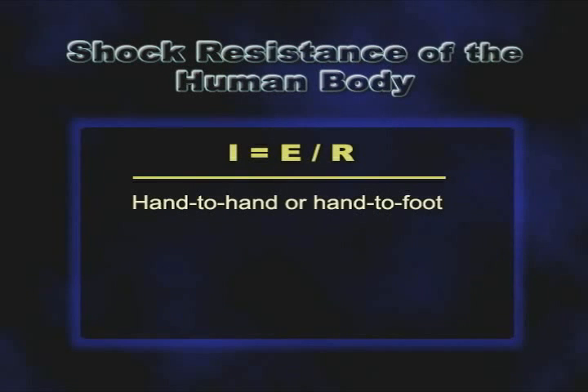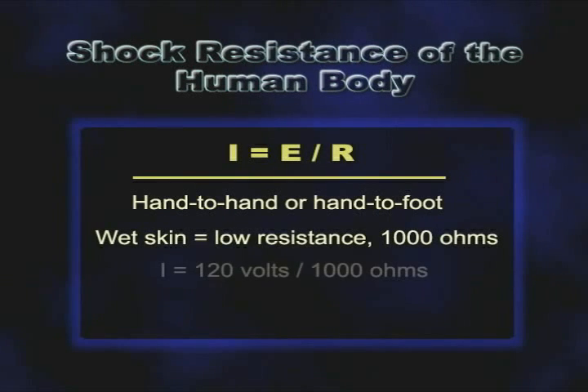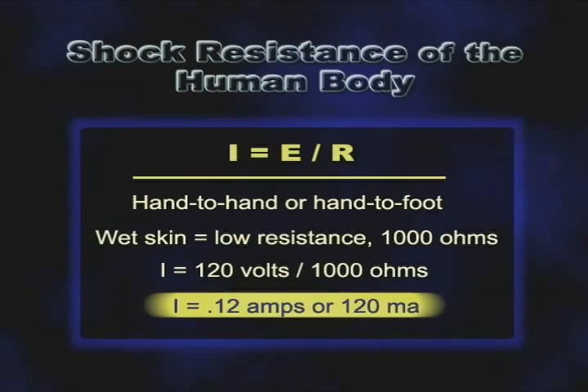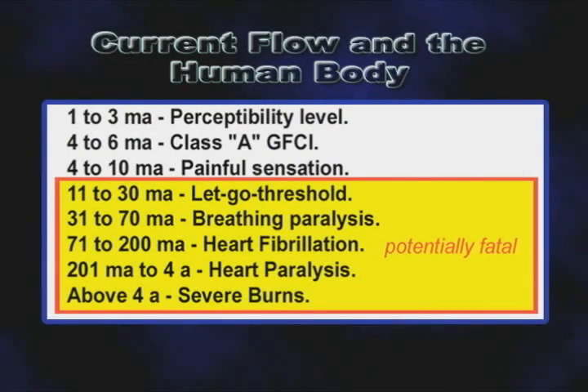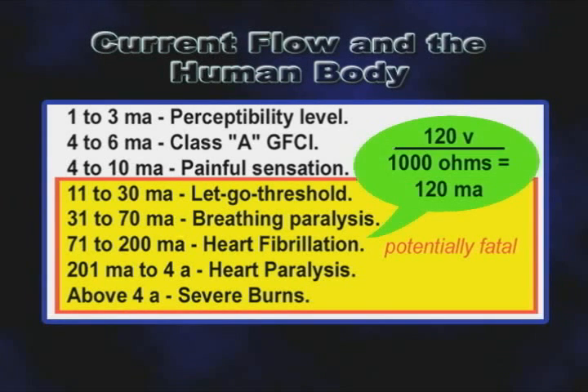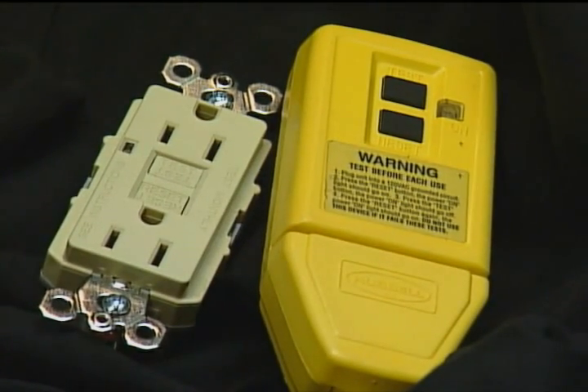Let's examine the hazard of shock. Using Ohm's law, we can see that an average person with wet skin will have a little more than one-tenth of an amp of current flow through their body at 120 volts. Even very small amounts of current flow can cause death. A hard-working employee generating a heavy sweat is at great risk for lethal levels of current flow. In industrial environments, most of the exposed surfaces of a building are considered conductive paths. A GFCI is one of the best devices ever invented to prevent death by electrical shock. This next video illustrates just how quickly a simple electrical repair can become a tragedy.